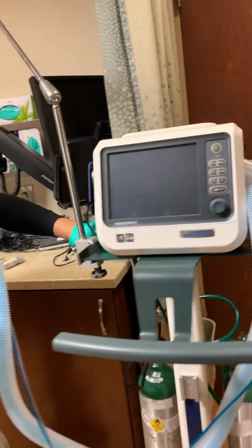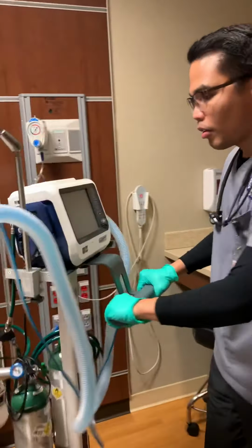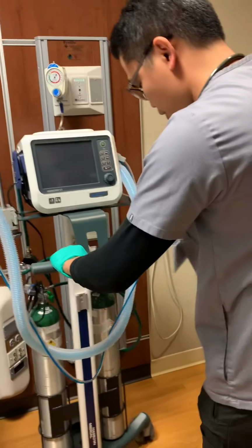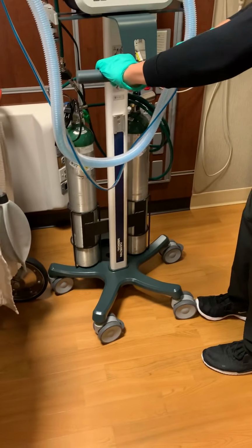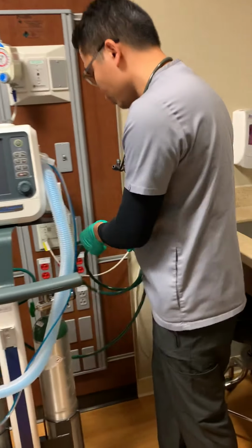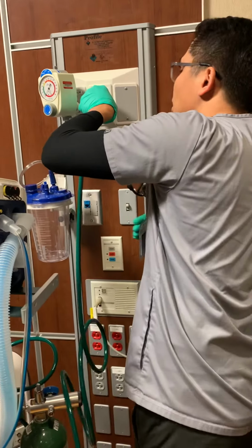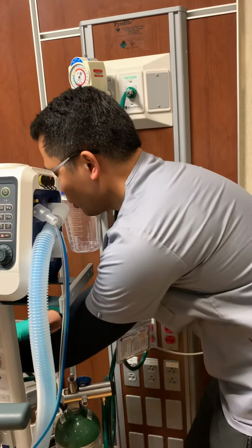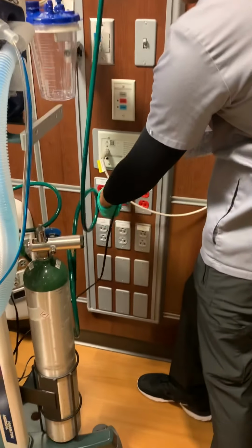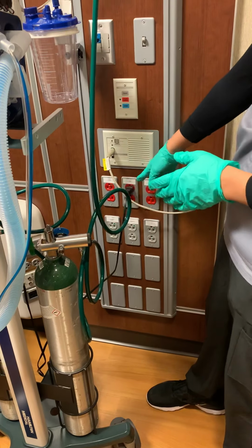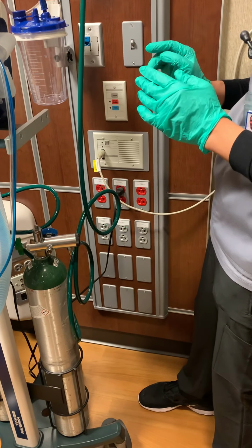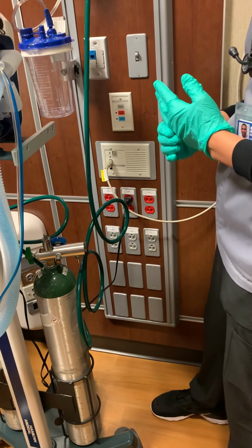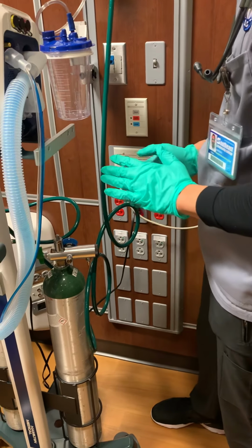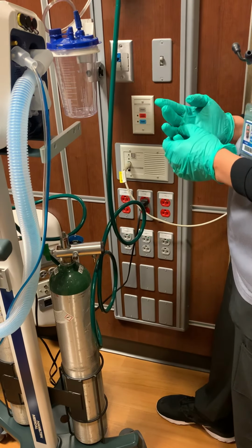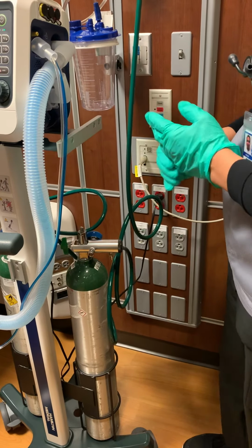So with the ventilator, make sure we hook it up here on the patient's bedside. So make sure we secure it by locking the wheels, and then make sure we have the oxygen tubing hooked up to hear the click sound, and then the cord should be inserted in this red electrical outlet. The reason why we hook it up in the red electrical outlet is that for cases like there might be a shutdown of electricity, so it will switch directly to backup battery or anything. So after that, make sure we turn this one on.